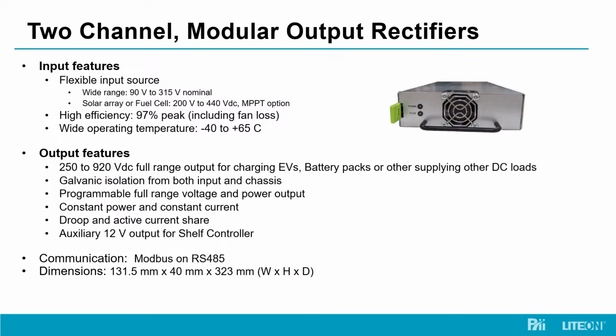At the heart of a DC fast charger is the rectifier itself. What you see here is a flexible input source rectifier where the input would be 90 to 315 volts AC, or a 200 to about 440 volt DC input option. I say option, but it's really all in the same rectifier. This allows it to be used in a number of different use cases, whether typical grid voltages or a DC input, perhaps from a battery source or a fuel cell source, the latter two being ones where you can essentially ensure it's a green renewable energy source.